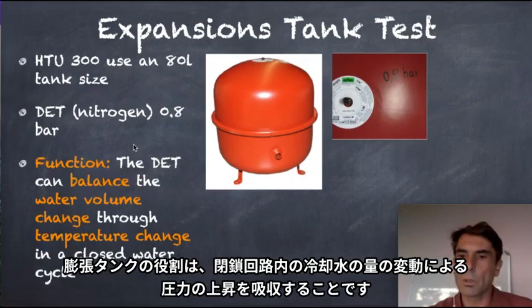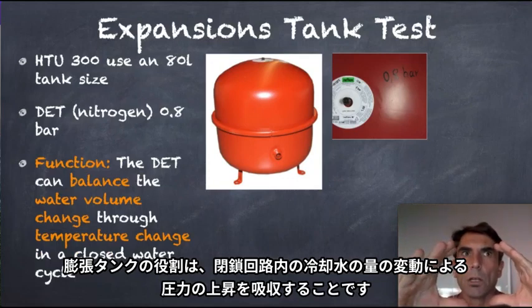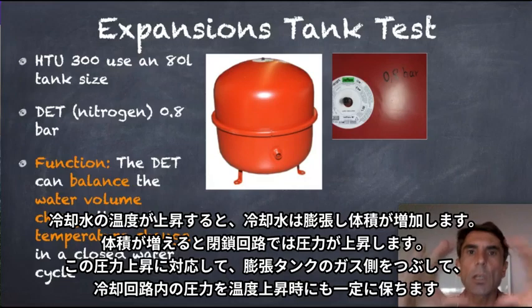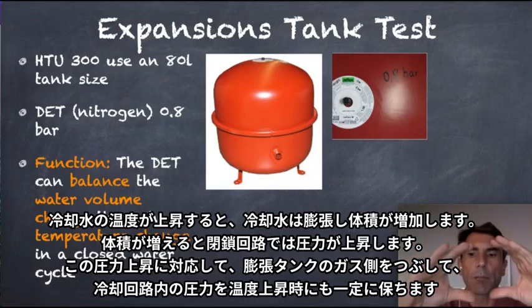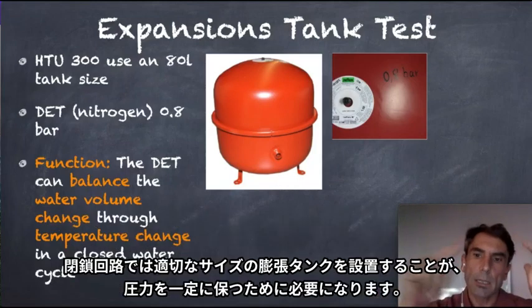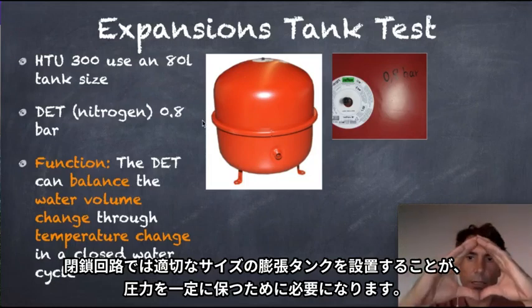Okay, and the important function of an expansion tank is to balance the volume change in a closed water cycle. If you have a closed water cycle and you heat up, the water will start to expand. And if the water expands, the pressure will increase. So that we can keep the pressure stable, we put the expansion tank in between, which compensates the volume change through temperature. So it is very important that a closed cycle has an expansion tank with the right size.